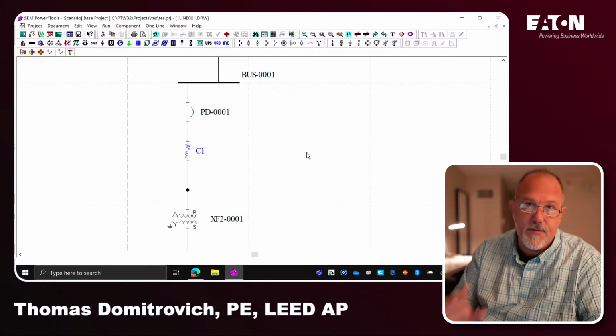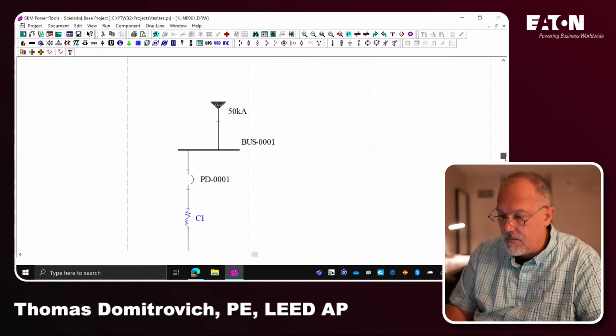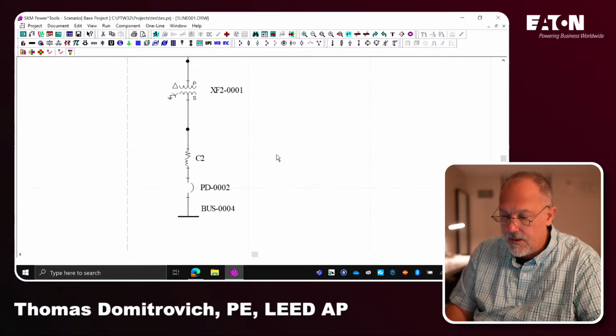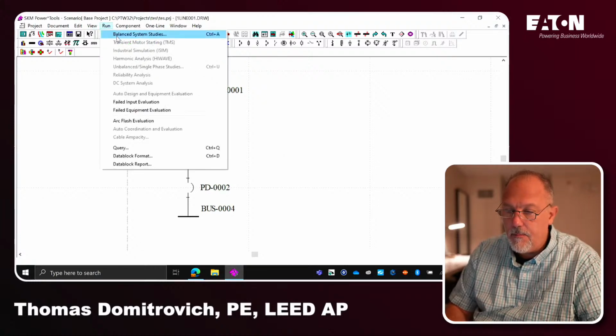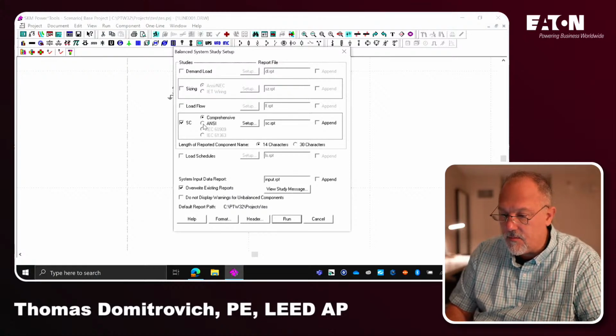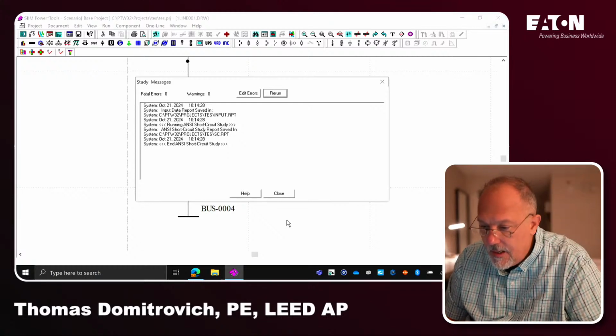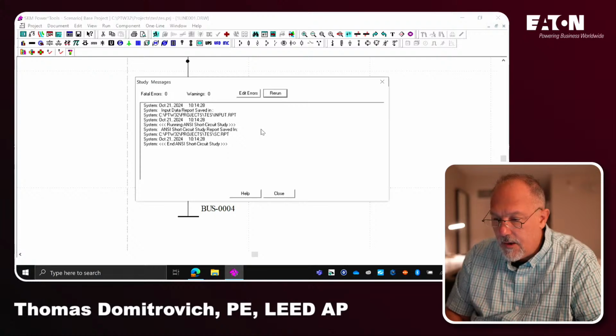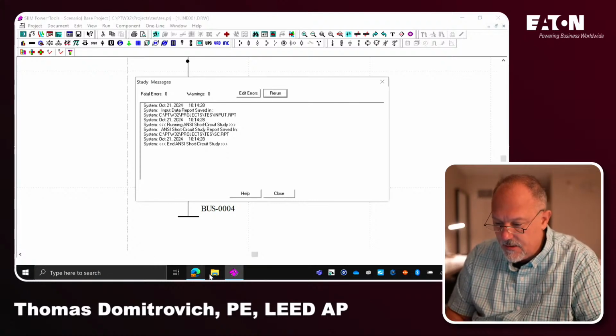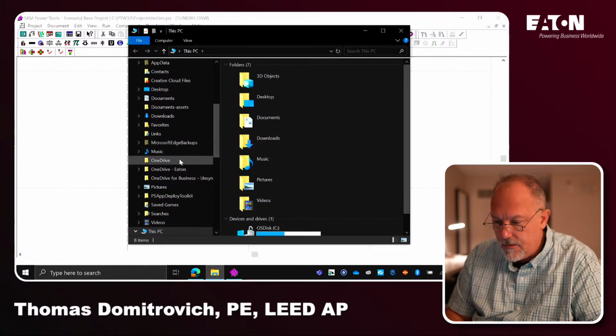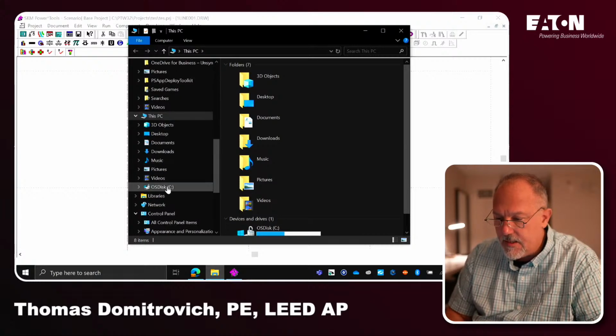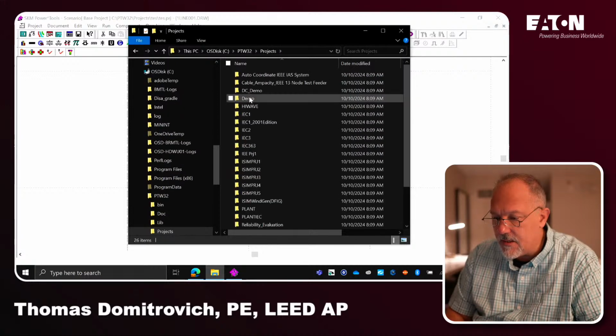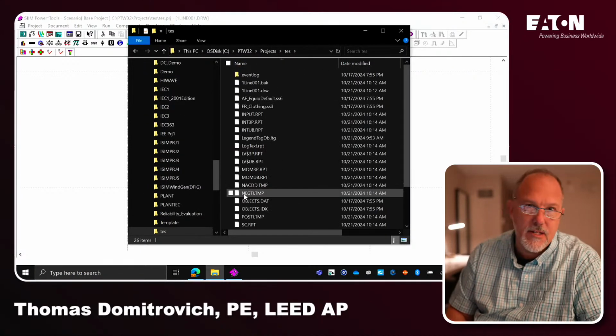All right, so I have defined the source. I defined the primary and secondary conductors. And I'm going to run the fault current. So I'm going to go run, balanced system studies, short circuit. I am going to run the ANSI, because we used ANSI rules of thumb the whole bit. And I'm going to hit run. 0 errors, 0 warnings. And it says it's saved. Where's it at? PTW32 projects TES. So if I come here to my folders, C, PTW, projects, and I go down to TES because I forgot to put the T at the end.